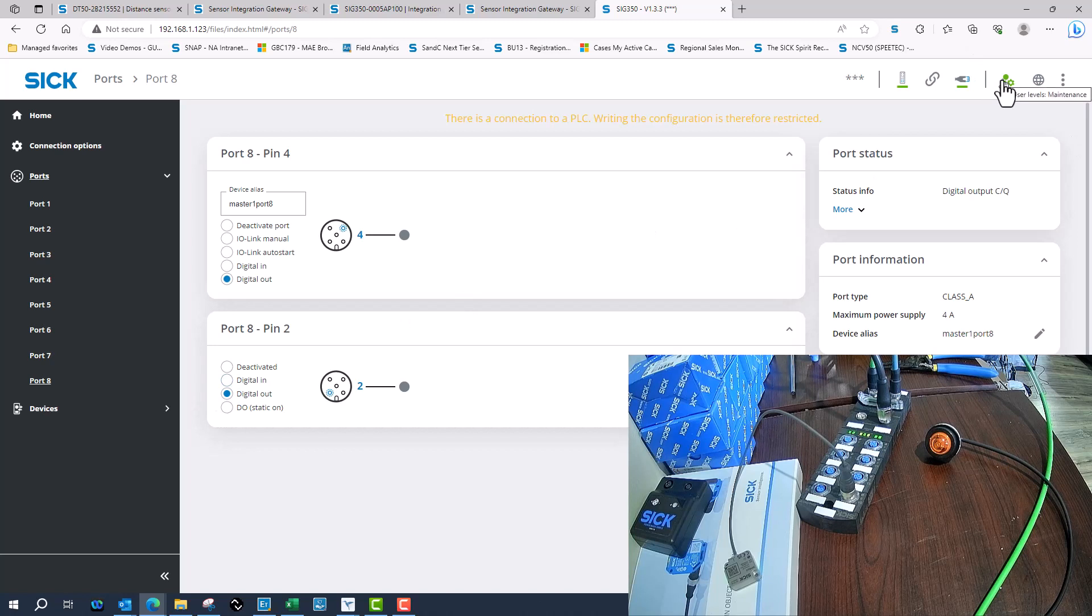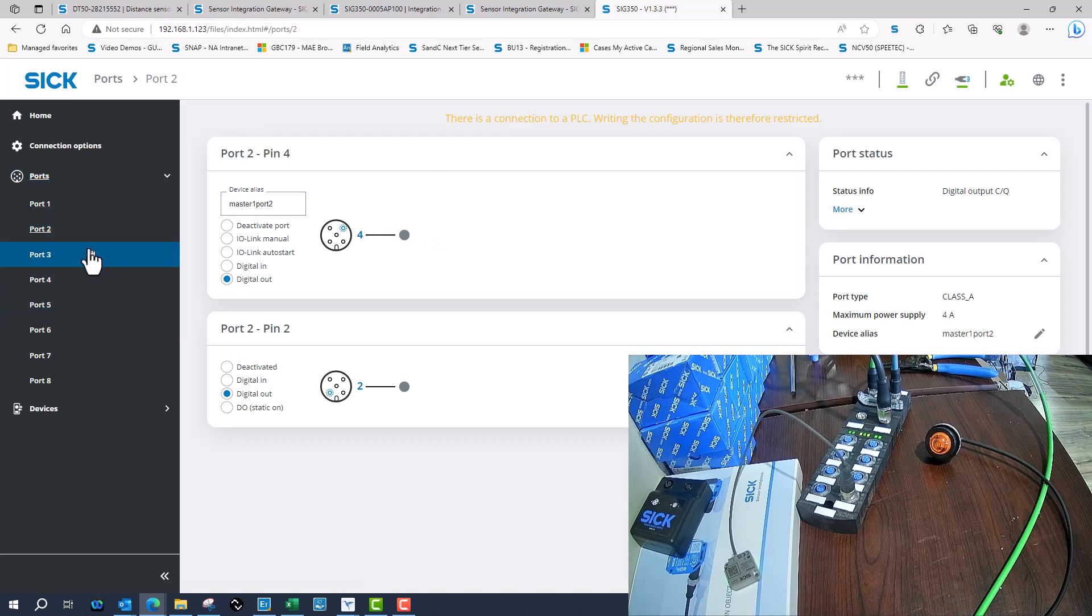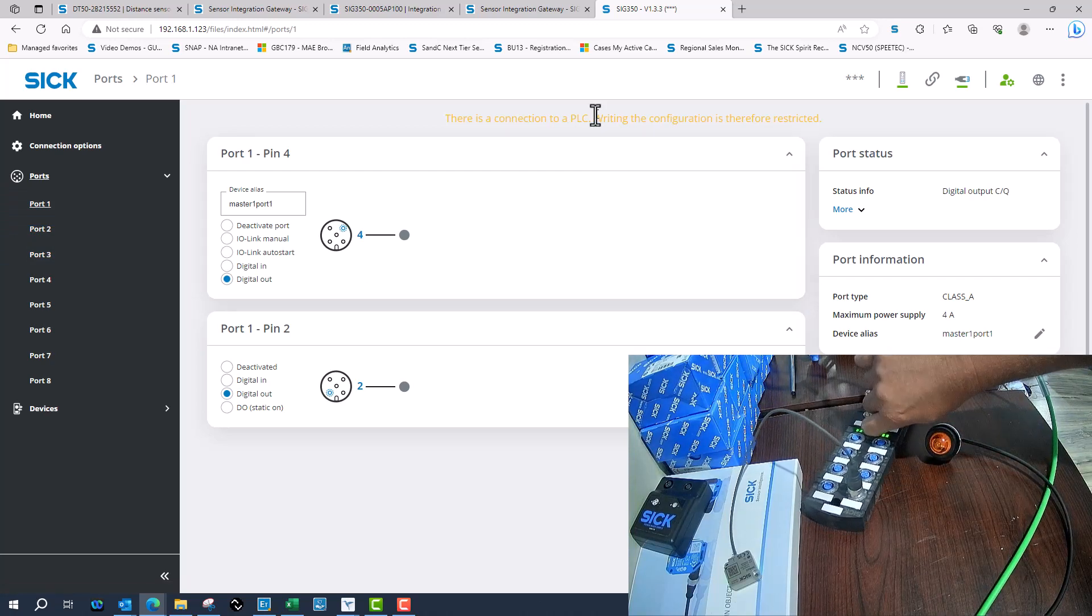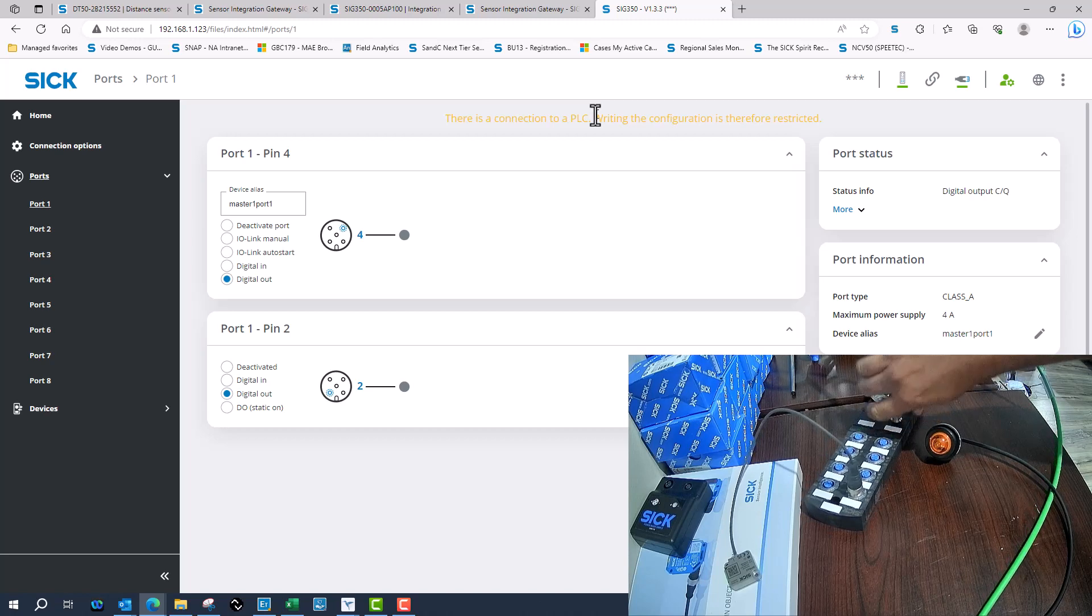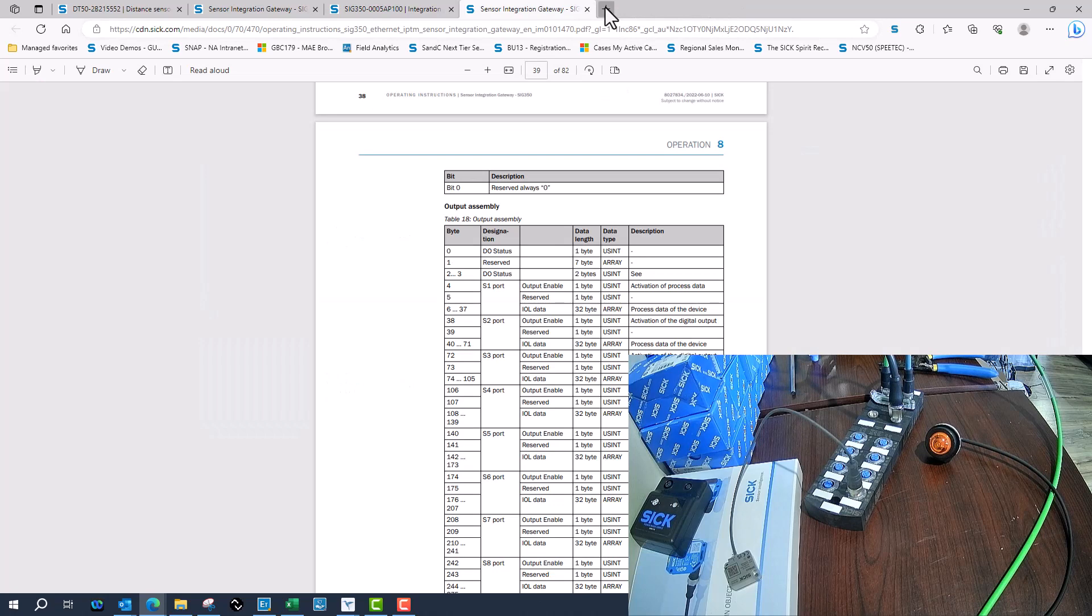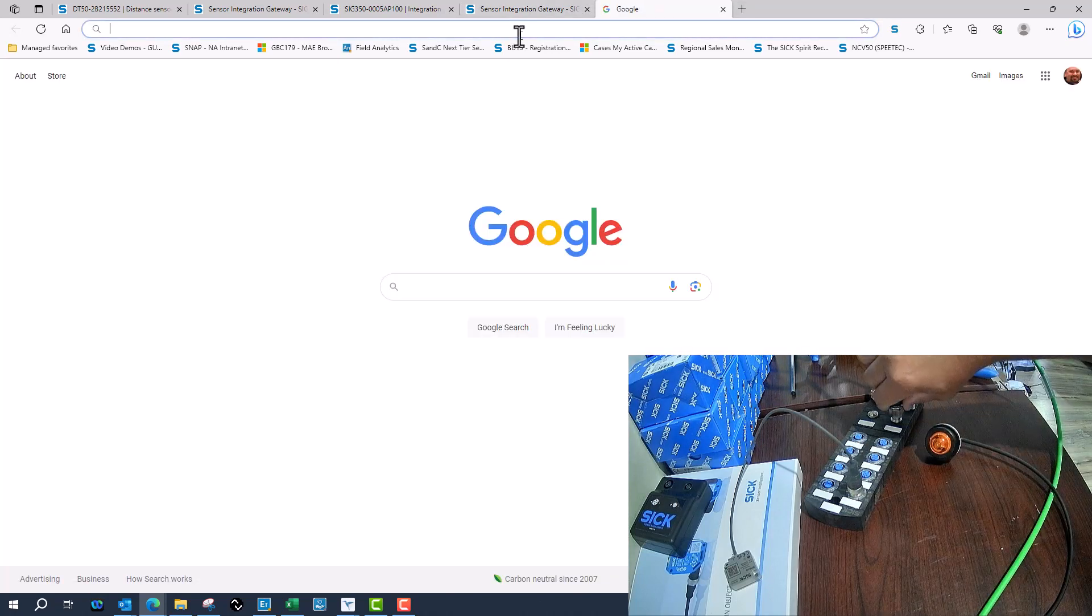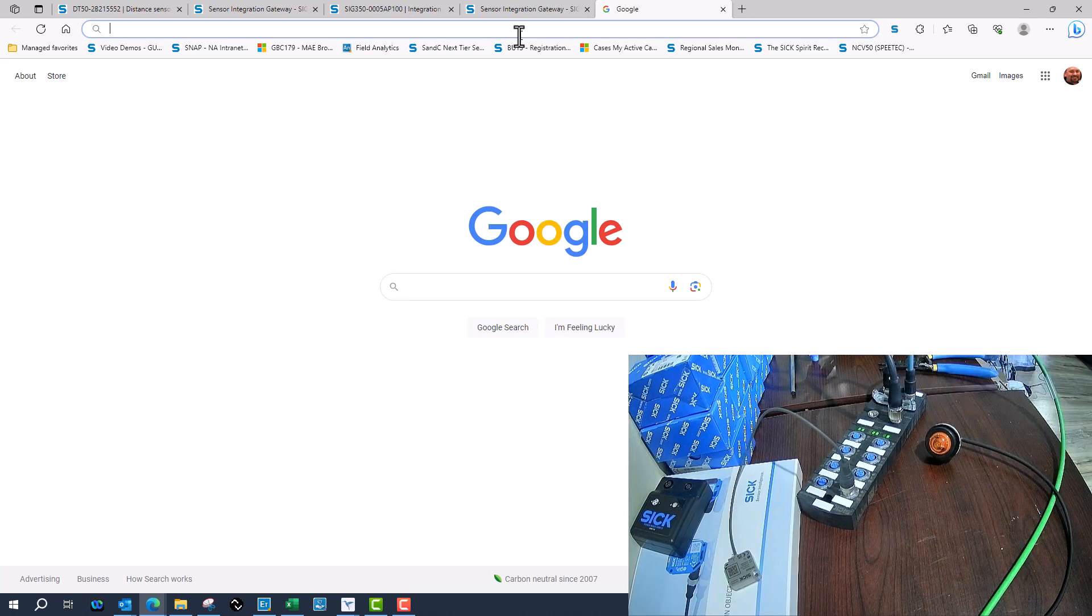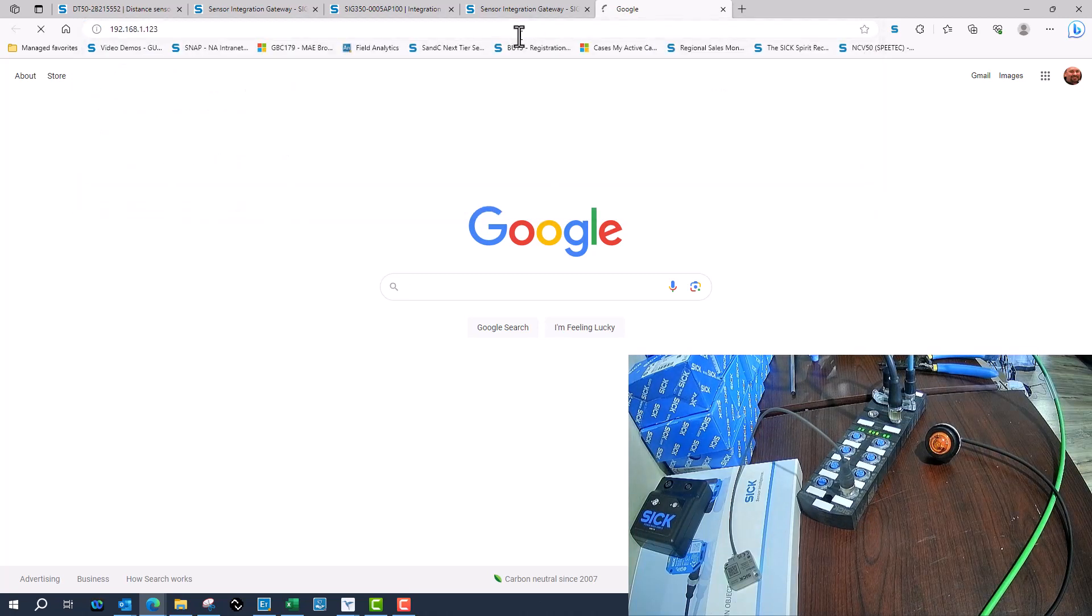Also make sure you logged in, the password is 'main'. You can find that on one of my previous videos on how to set up and map all the IO. What I'll do is just cycle power on the SIG 350 and close out just to verify that all of my settings took place. The last thing you want to do is make a lot of changes and think you've got everything connected correctly and it doesn't work, so I always verify by cycling power.